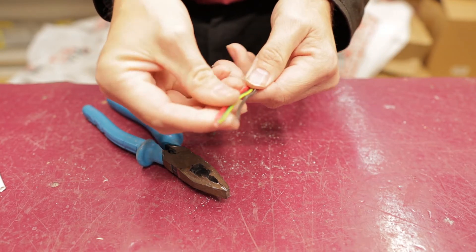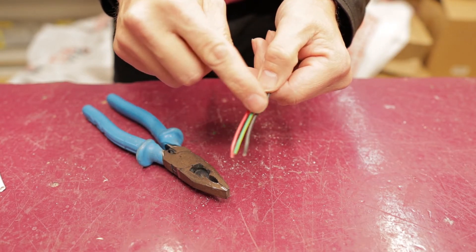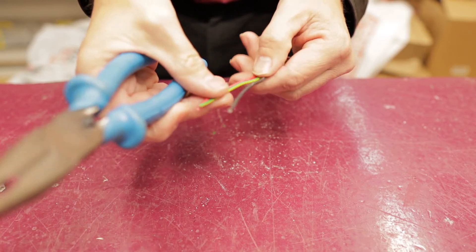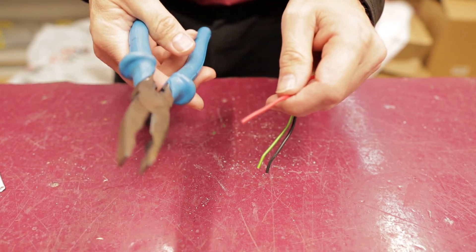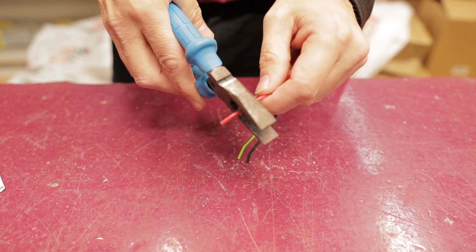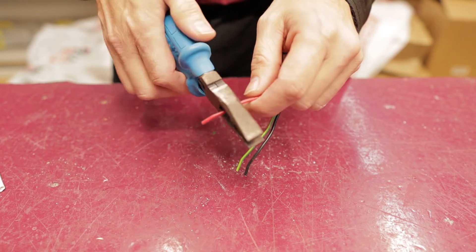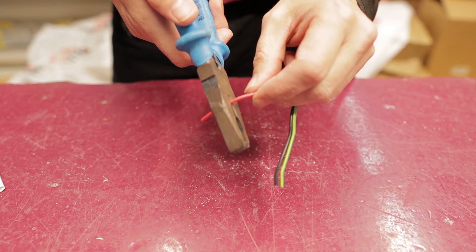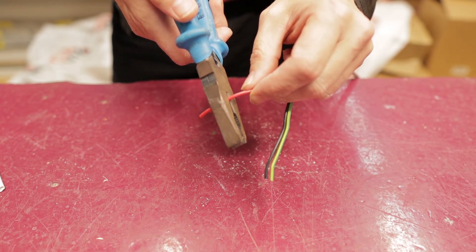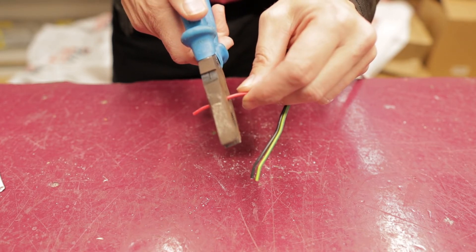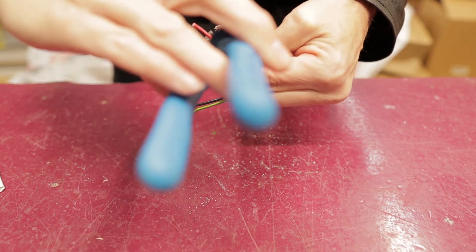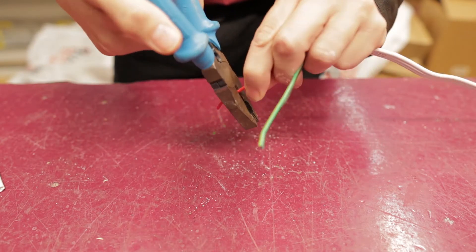Now I need to remove the insulation from my individual wires. So I'll choose the active and to do this is really a knack. What you need to do is put your pliers on the conductor, again slightly bite down on it. We're not trying to cut through, really important we don't try to cut through, and then we just spin our pliers around like this.